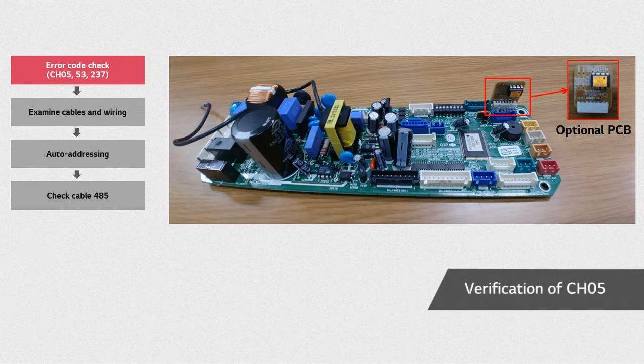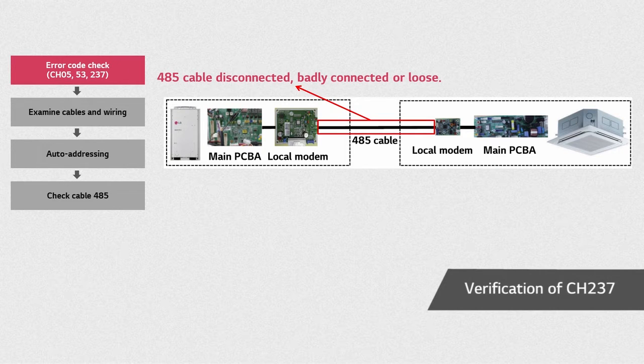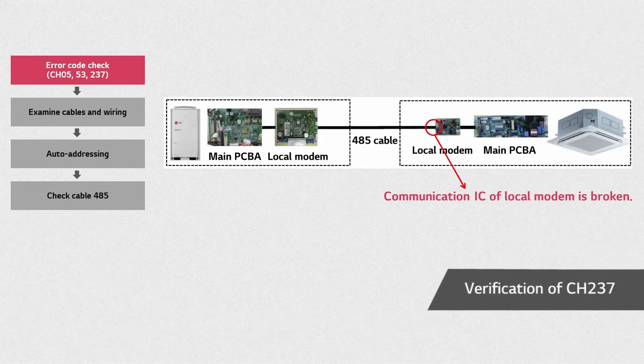If the optional PCB needs to be replaced, please proceed with the auto address setting. Error CH237 occurs when communication between the IDU's local modem and ODU's local modem fails. When this error occurs, you should check whether the 485 communication cable is disconnected, badly connected, or not fastened to the communication terminal block. Sometimes, there may be damage in the IDU's local modem communication IC which is connected to the ODU.